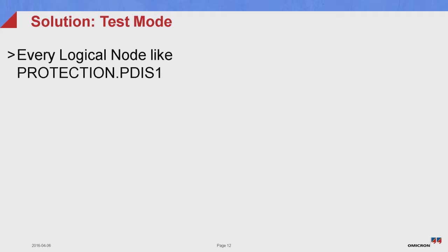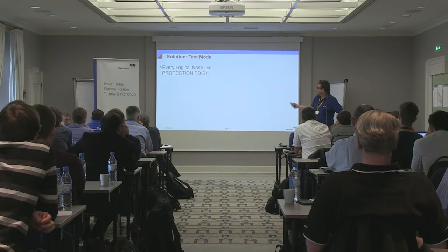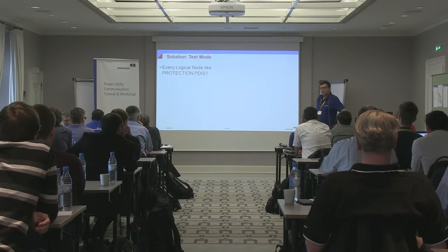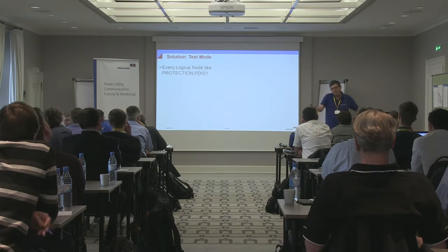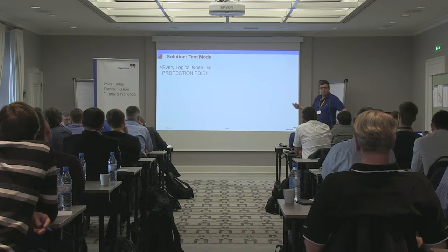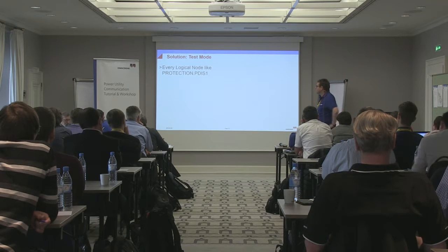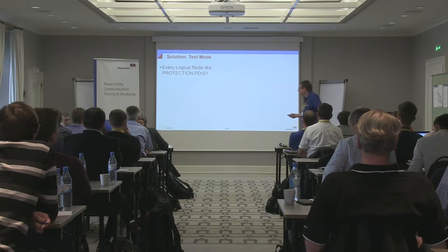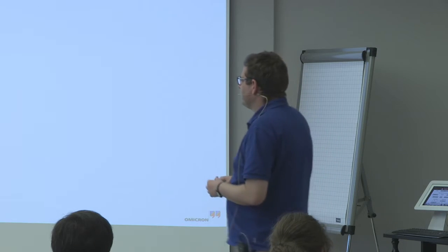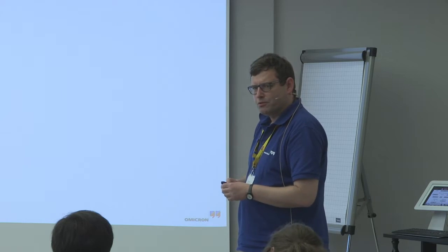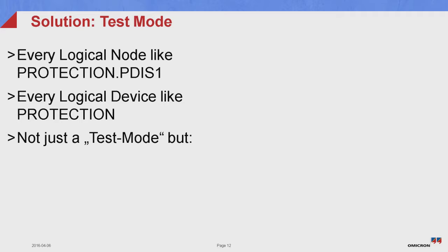So the standard says every logical node, you remember, for instance, there's an example here, PDIS1, so it's the set 1 for the protection functionality, can be set to this test mode. So you can, for instance, set zone 1 into test, and keep zone 2 in normal operation, so it's really possible. If it makes sense, it's something you can discuss, but anyway, it's possible. Additionally, you remember the structure that we defined, it's also possible to set an entire logical device to the test mode. So you say, okay, now the entire distance protection, or the Siemens devices, where every single protection function is its own logical device, or you have a huge one combining everything, you can set this device also to a test mode. So this is one thing that we have in the standard.